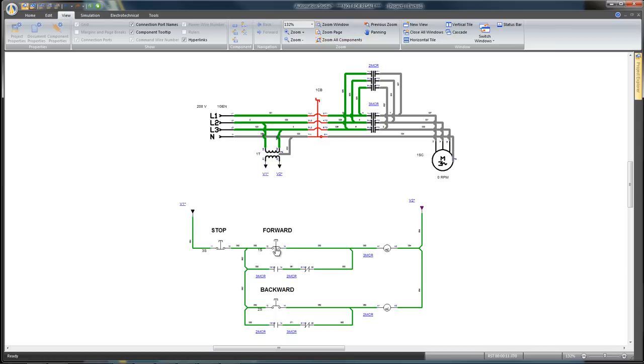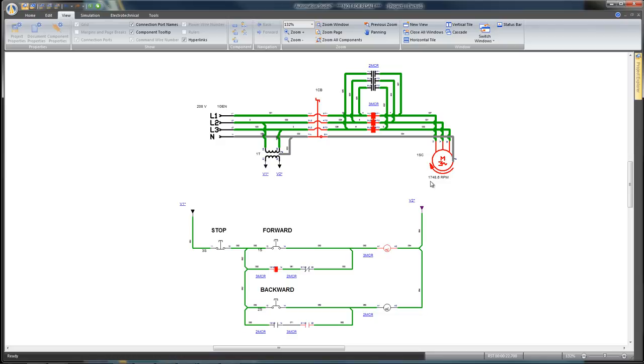It will also activate the associated normally open contact to maintain the forward coil and it will deactivate the normally closed contact and the backward command. The motor starts with a positive speed. Notice that the motor speed will increase. An arrow shows the rotation direction.